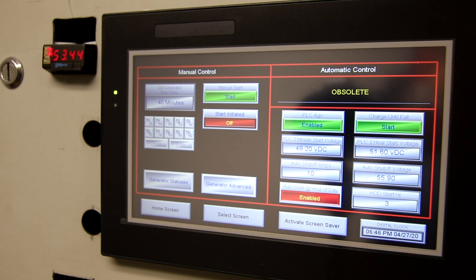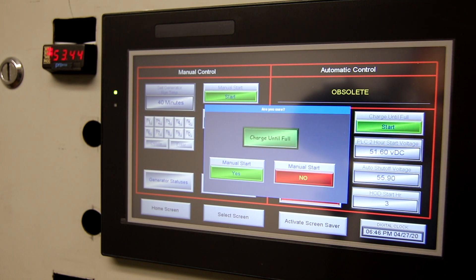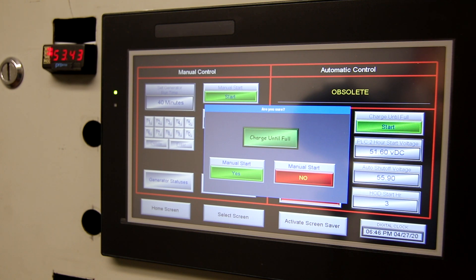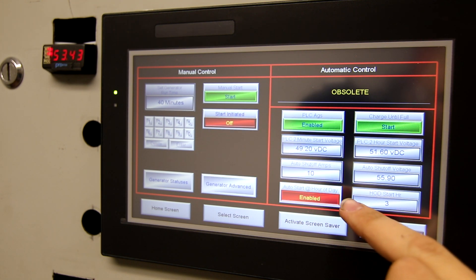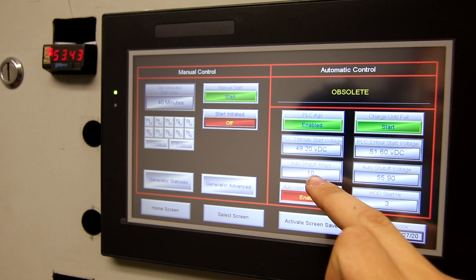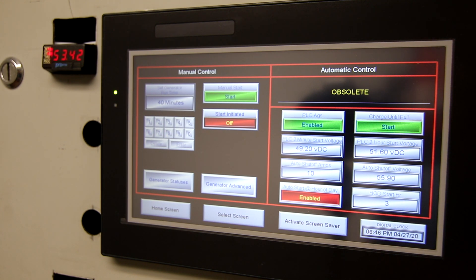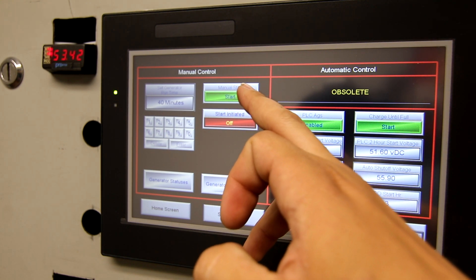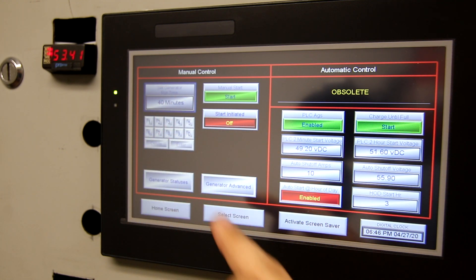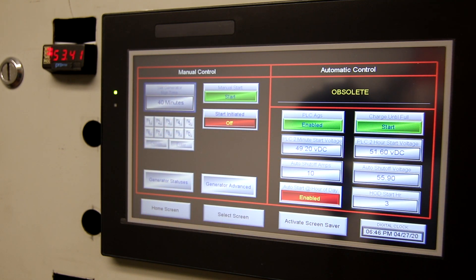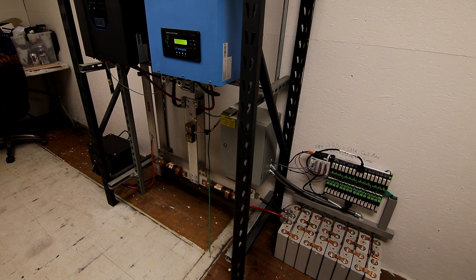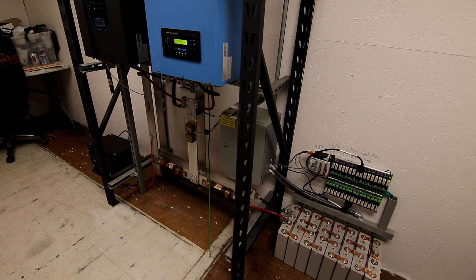I also have a feature that's charge until full and I can select that and it'll do a full charge not based on time and run until it reaches this 10 amps shut off as well as the 55.9 volts shut off and then I also have a manual start where I can enter a time here with the keypad and that will run the generator manually for a programmable amount of time. So those are just some of the features I've implemented in my system but the main thing is that it's really cool with this battery pack how it takes the brunt off the rest of the batteries that are the expensive ones.